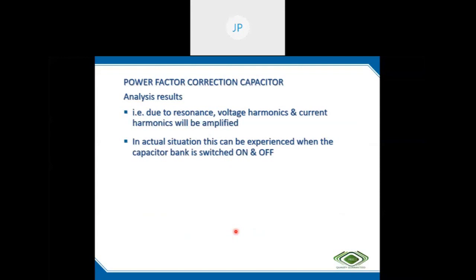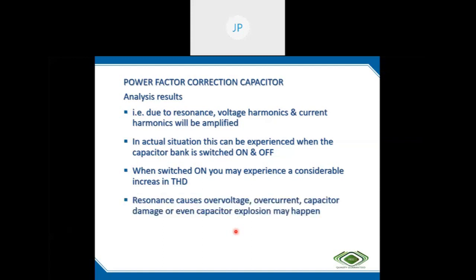Due to resonance, voltage and current harmonics are amplified, and we can visualize this. If we switch on a capacitor bank and see some increase in THD, that indicates that harmonic amplification is there. If we switch it off, it will reduce. The effects include voltage and current distortion, capacitor damage, overcurrent flow, and even capacitor explosion may happen. To avoid such adverse effects, suitable mitigation measures must be adopted.